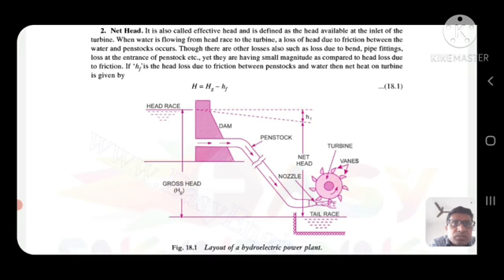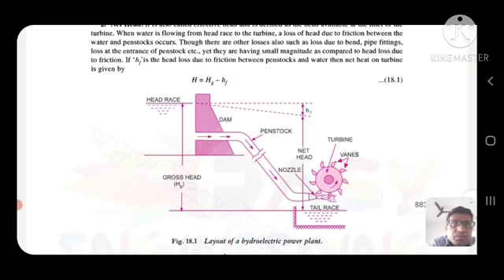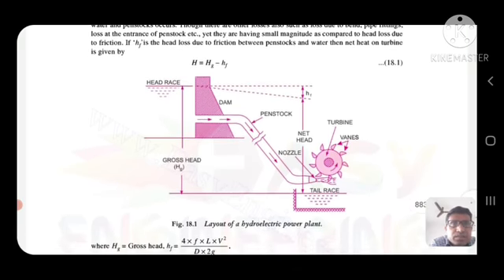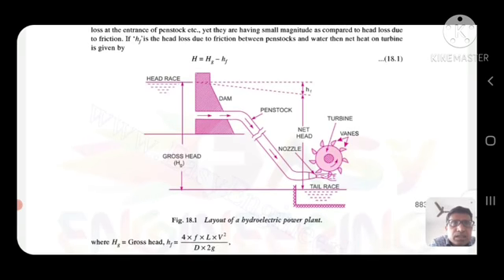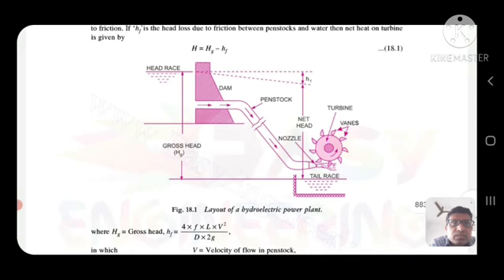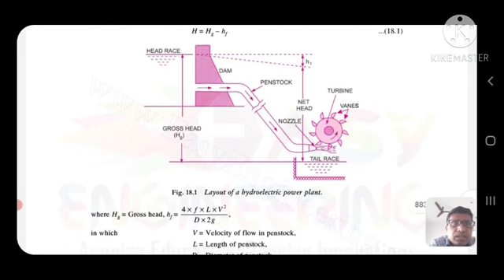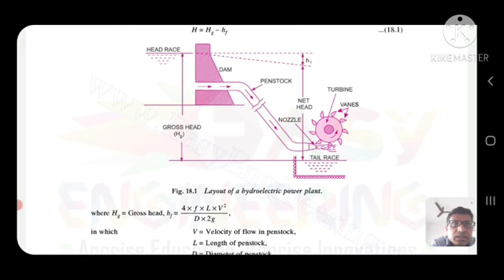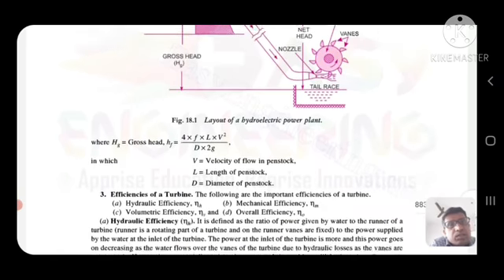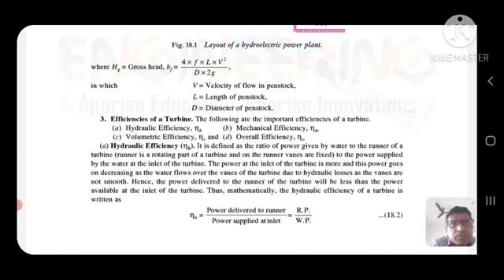If HF is the loss of head due to friction between the penstock and water, then the net head on the turbine is given by: H = Hg − HF. The gross head Hg, and HF = 4fLV²/2gD, where V is the velocity of flow at penstock, L is the length of the penstock, and D is the diameter of the penstock. This is the layout of the hydraulic power plant showing dam, penstock, nozzle, tail race, and vanes.